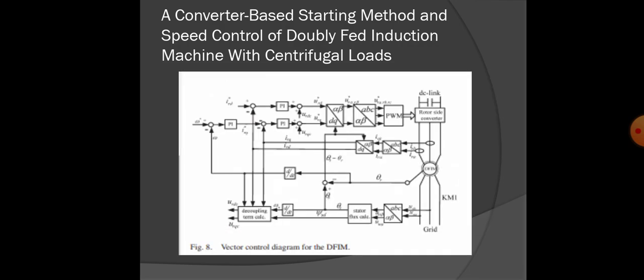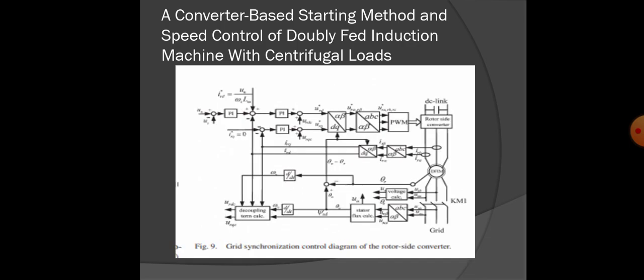And this is the vector control diagram for the double fed induction machine, which has the converters and DC link, the rotor side converters, and the decoupled errors with the PI controllers. All these are converters used in this system. And there is the grid synchronized control diagram for the rotor side converter. We have the power supply, and it is a closed loop function which controls the speed and starting methods of the system. Thank you, sir.